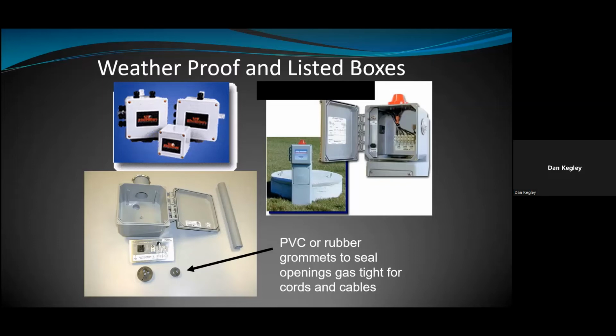And again, like I said, if the conduit goes into the ground, you should also have some duct seal or something to seal out the ground moisture getting into that box. The code does also say there should be a little weep hole in there. It says it can be an eighth to a quarter of an inch. So even though these are covers that are closed tightly, inevitably you can still get moisture developing in there through condensation, or if there's a leak because the putty gets dry over time. The code does require a little weep hole, an eighth inch to a quarter inch hole, usually in the bottom side, to be installed in a closed junction box like this, so that it doesn't keep collecting water and more moisture over time.